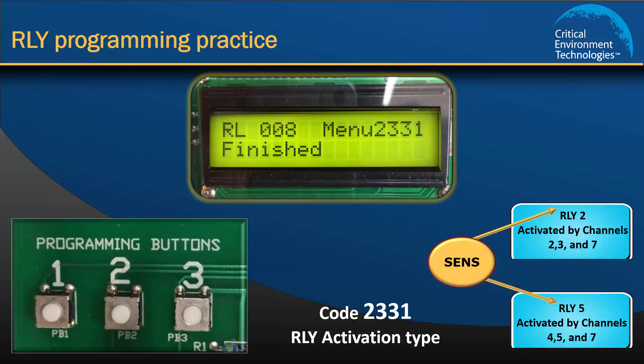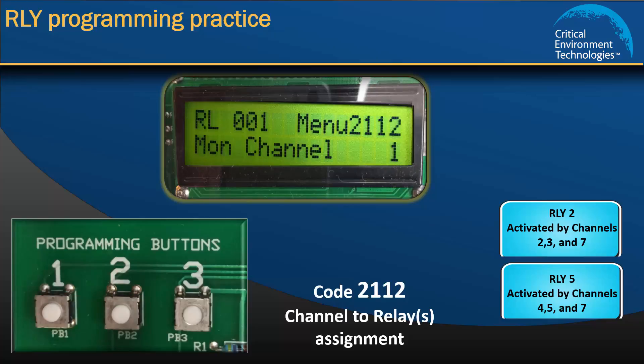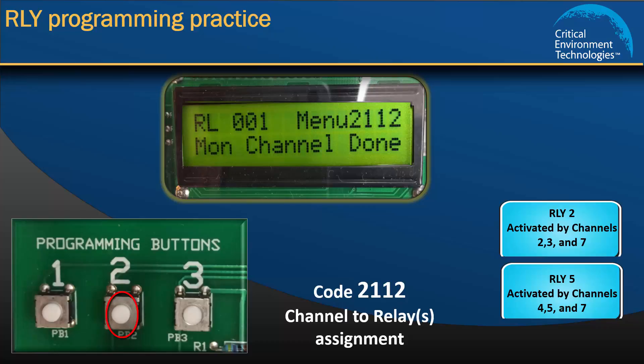Now we need to tell the relays which channels to monitor. For every PDC, the factory default activation type is set to All and the relay-to-channel numbers are set 1 to 1, meaning Channel 1 is assigned to Relay 1, Channel 2 to Relay 2, Channel 3 to Relay 3, and so on. Using the programming buttons, enter code 2-1-1-2 to bring up the Relay to Channel assignment menu. The display will start at Relay 1, Channel 1. We are not concerned with Relay 1, so press 2 to save and the display will show "Mon Channel done."